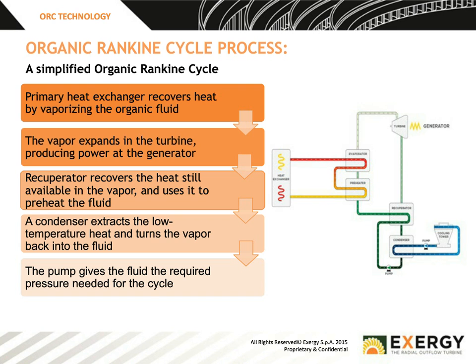This heat exchanger allows the organic fluid to vaporize, making the organic fluid into a gas. That gas is taken to the organic Rankine cycle turbine, which in this case is an EXERGY-specific turbine. It expands within the turbine, driving the generator, and this is what gives us the energy. After that, it leaves the turbine, still as a vapor, where it passes an item which is unique in the ORC cycle, which is called a recuperator.